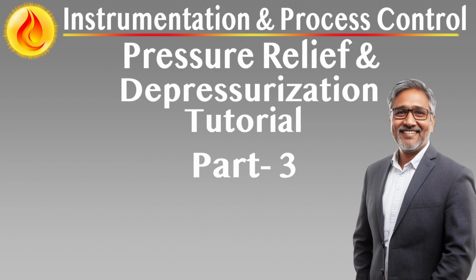Effective emergency depressurization design must ensure that equipment integrity is preserved during high-stress events such as fire exposure or significant leaks. Depressurization systems must reliably and rapidly reduce pressure within safe limits, taking into account thermal effects, material limitations, and flare system capacity. Key elements of depressurization design include valve requirements.